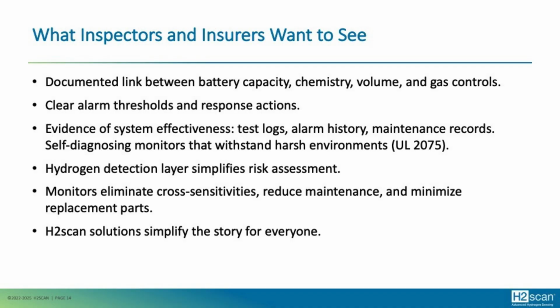And it really helps when you have smart systems. Today we have the ability to have safety systems such as sensors that have self-diagnosing capabilities and also self-calibration capabilities, so that they're doing all these things automatically, so that you don't have to worry about it. And as long as it's built properly with the self-diagnosing characteristics, it will alert you if something is not operating correctly. There are so many sensors out there that could have blocked signals, so the green light is on saying it's operating properly, but it really is not, because the signal's been blocked. So choosing a sensor that actually has these diagnostics is very important.